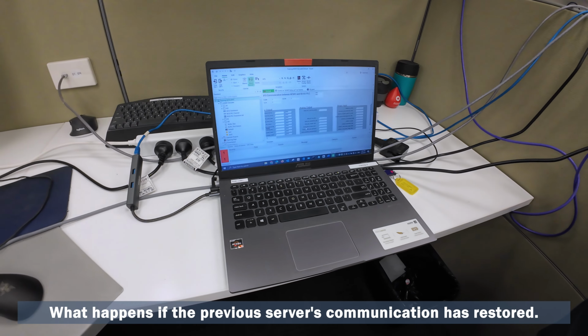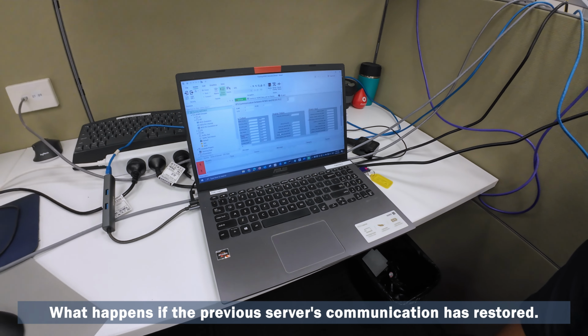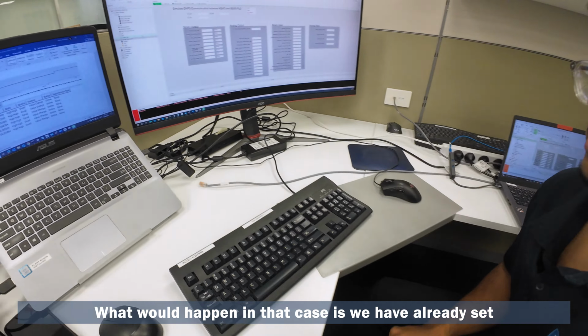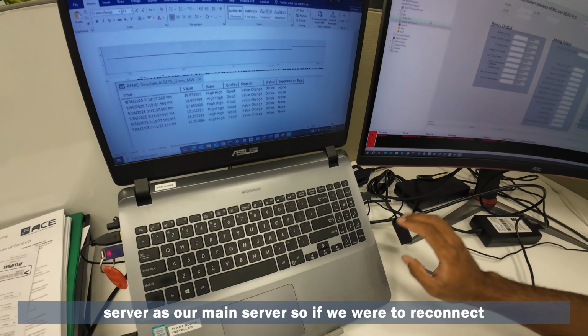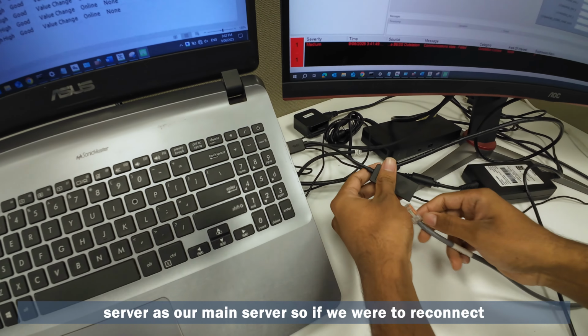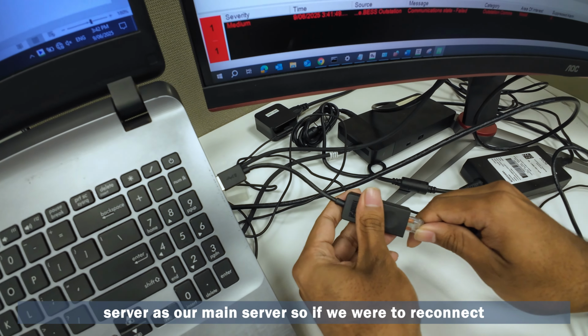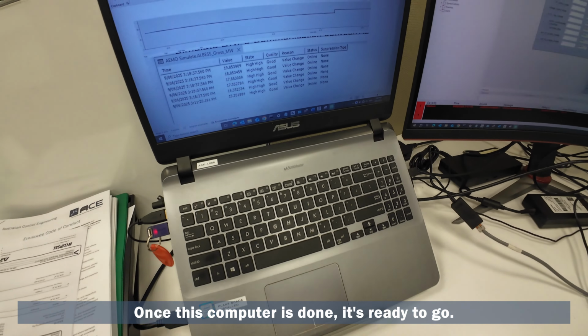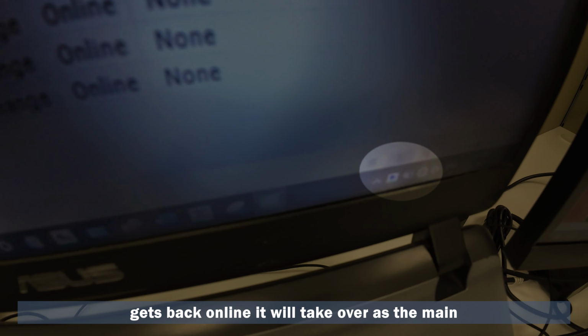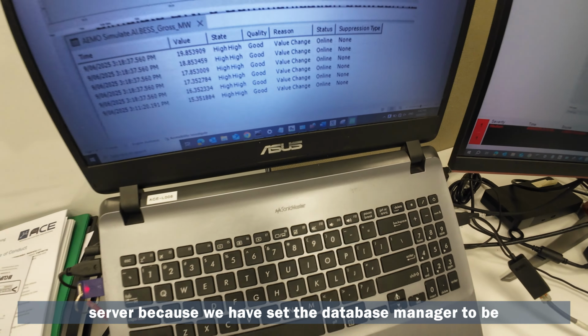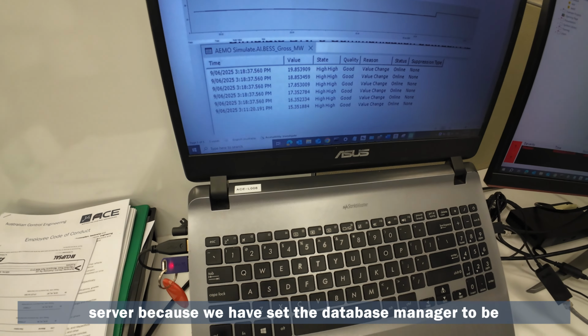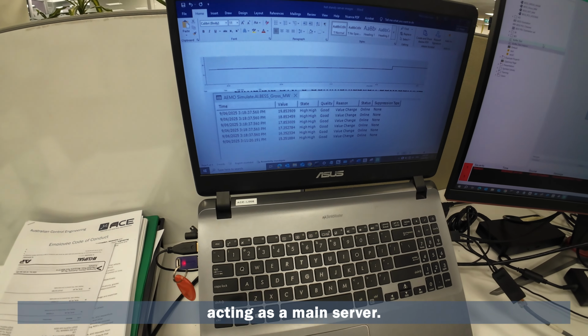What happens if the previous server's communication is restored? What would happen is, since we have already set this server as our main, if we reconnect the connection, once this computer gets back online it will take over as the main server, because we have set the database manager to act as the main server.